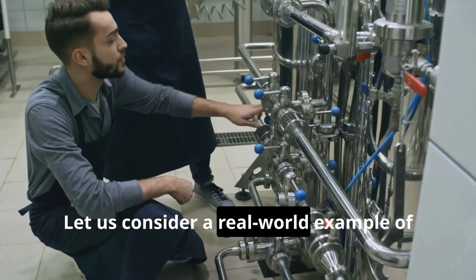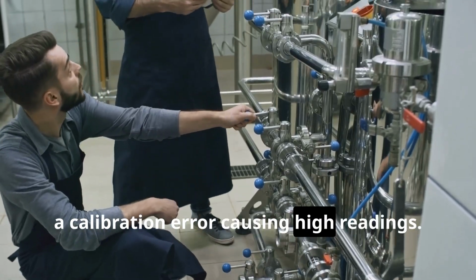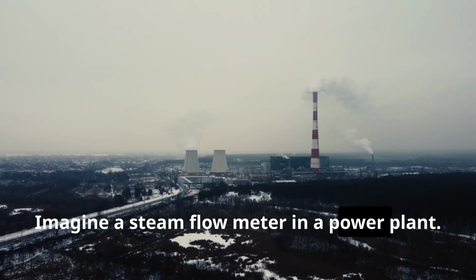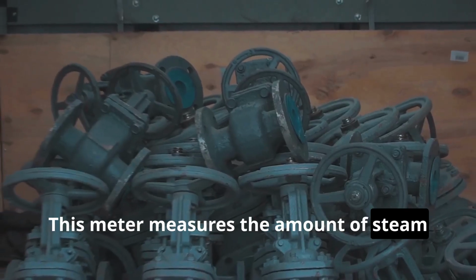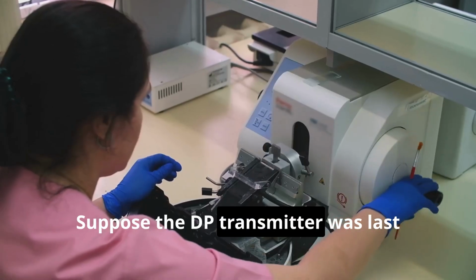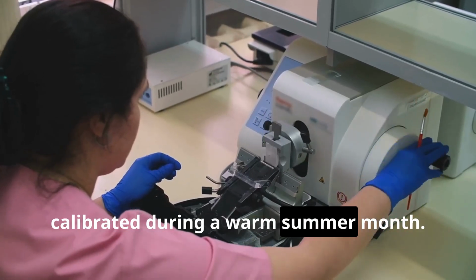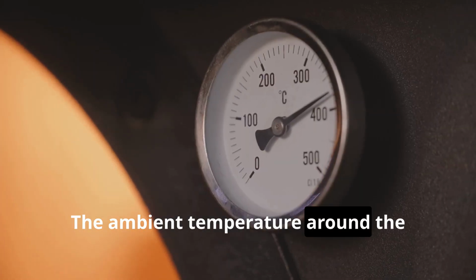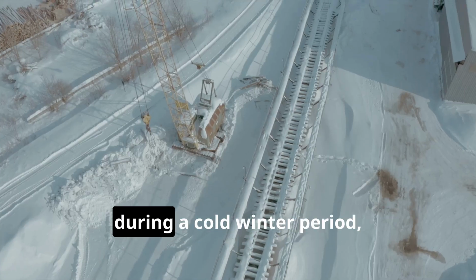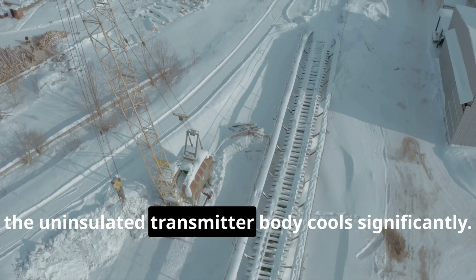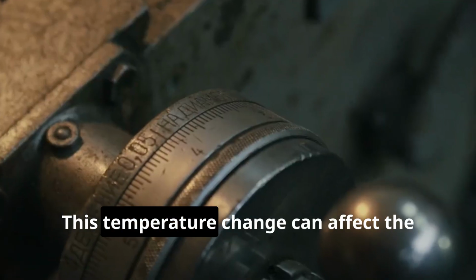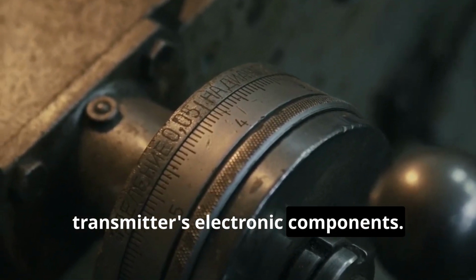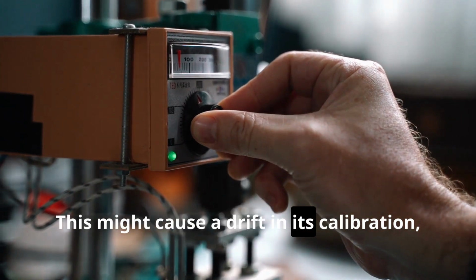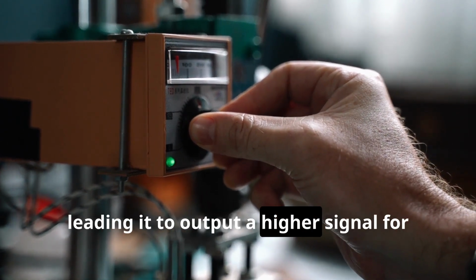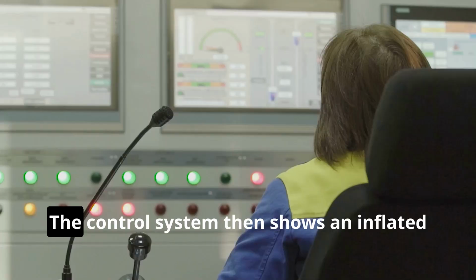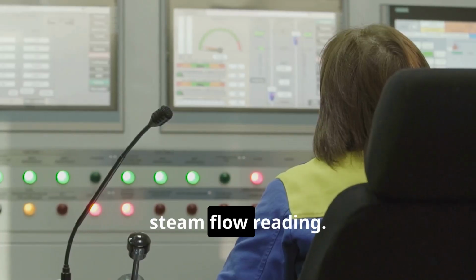Let us consider a real-world example of a calibration error causing high readings. Imagine a steam flow meter in a power plant. This meter measures the amount of steam going to a turbine. Suppose the DP transmitter was last calibrated during a warm summer month. The ambient temperature around the transmitter was high. Later, during a cold winter period, the uninsulated transmitter body cools significantly. This temperature change can affect the transmitter's electronic components. This might cause a drift in its calibration, leading it to output a higher signal for the same differential pressure. The control system then shows an inflated steam flow reading.